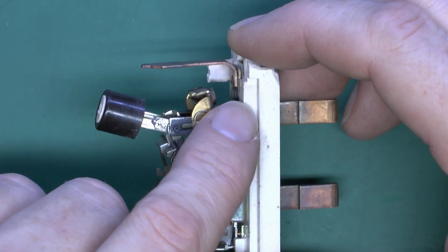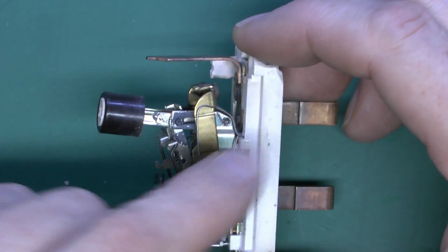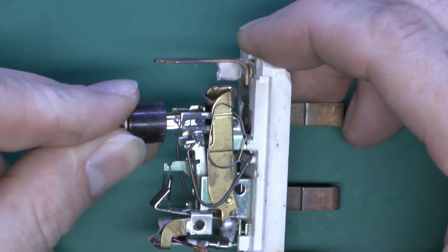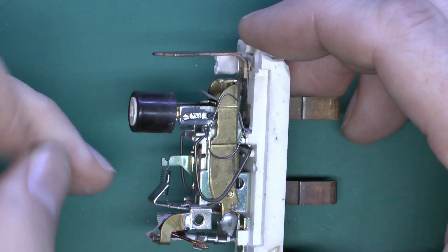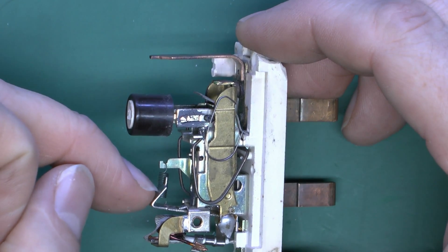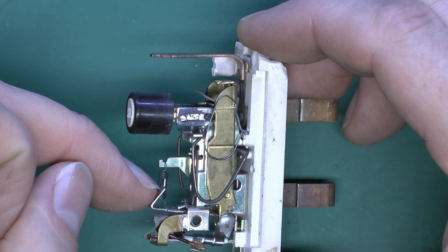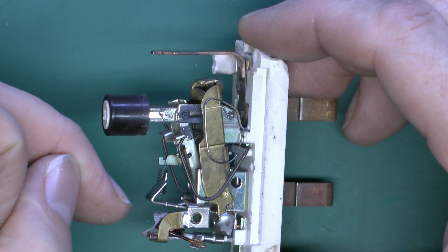It's actually sort of pressing it downwards slightly. So notice quite a big gap on the contacts there. And basically that's what you want, and you want it to open as quickly as possible, so obviously minimize any kind of arcing that you would get there. So again in the closed position, and then the button basically just presses on this angled piece, so it will spring open.